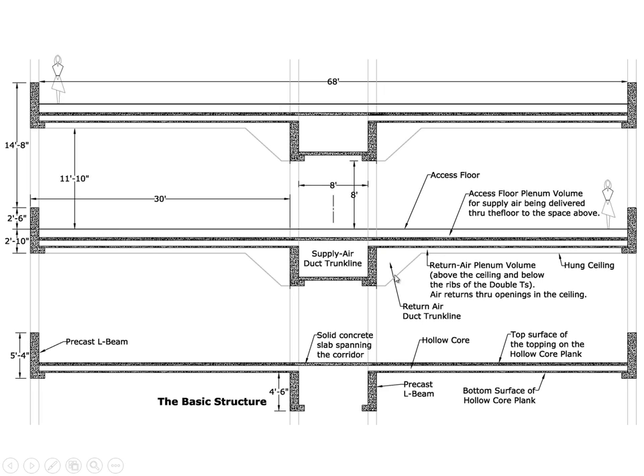Air passes from the supply air trunk line up into the plenum volume and flows south to supply that space and north to supply the other space. We're supplying air low and taking it out in the plenum volume high. With all of that, we've achieved a floor sandwich of 2 feet 10 inches, leaving a floor-to-ceiling dimension of 11 feet 10 inches. Again, we can decide whether to take advantage of this for daylighting or lower the overall story dimension as an economy measure to reduce the cost of the building.